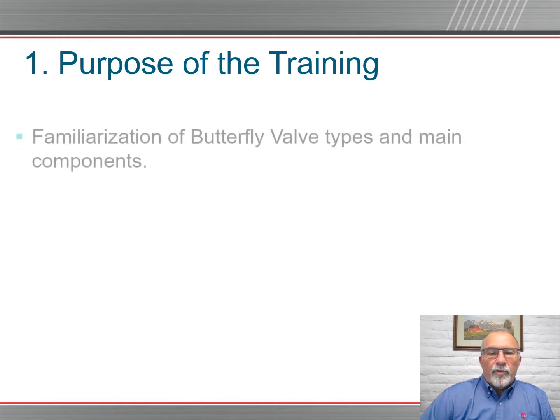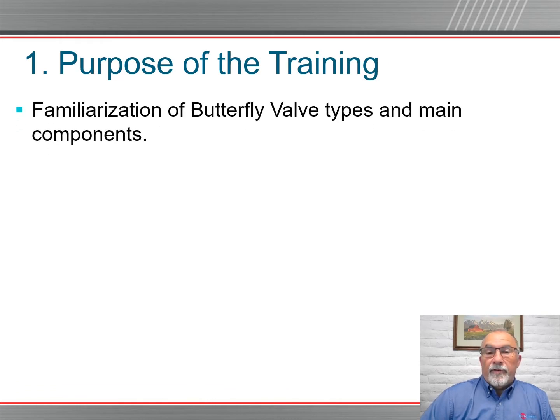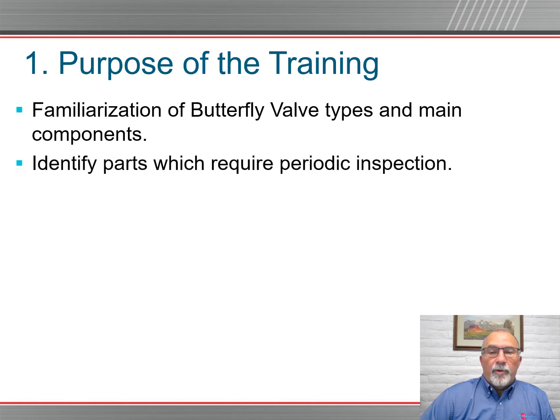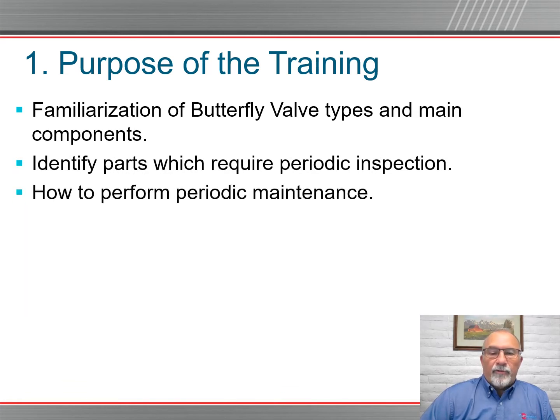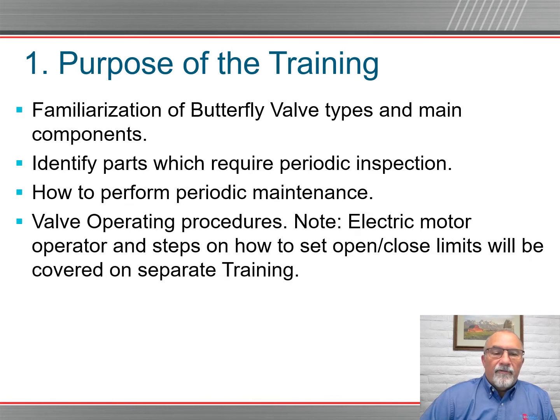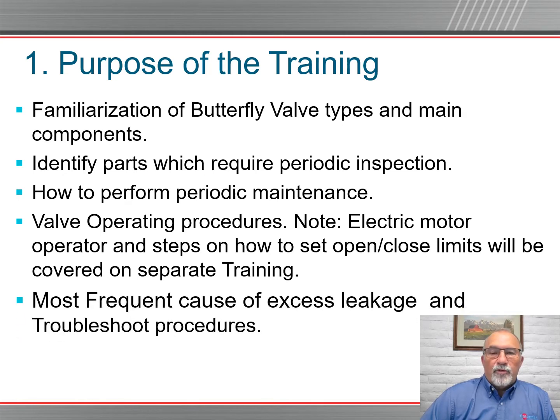The purpose of the training will include familiarization of the butterfly valve types and the main components, identify parts which require periodic inspection, how to perform periodic maintenance, valve operating procedures. Note, the electrical motor operator and steps on how to set, open and close limit switches will not be covered in this presentation. They'll be under a separate training. Most frequent causes of excess leakage and troubleshoot procedures and safety precautions.